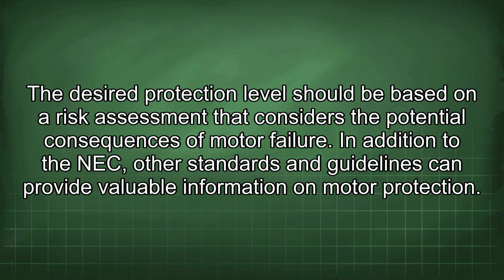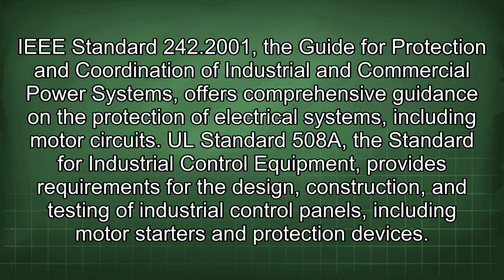In addition to the NEC, other standards and guidelines can provide valuable information on motor protection. IEEE Standard 242-2001, the Guide for Protection and Coordination of Industrial and Commercial Power Systems, offers comprehensive guidance on the protection of electrical systems, including motor circuits. UL Standard 508A, the standard for industrial control equipment, provides requirements for the design, construction, and testing of industrial control panels, including motor starters and protection devices.